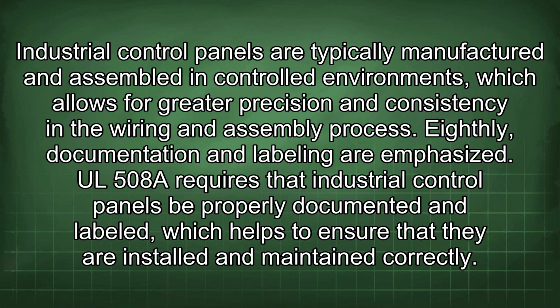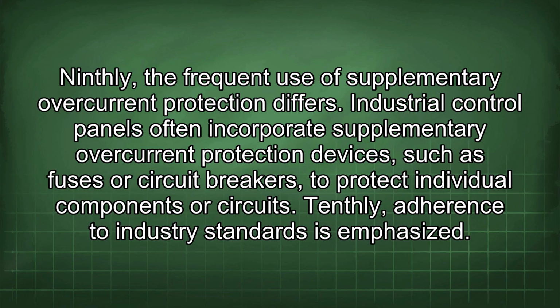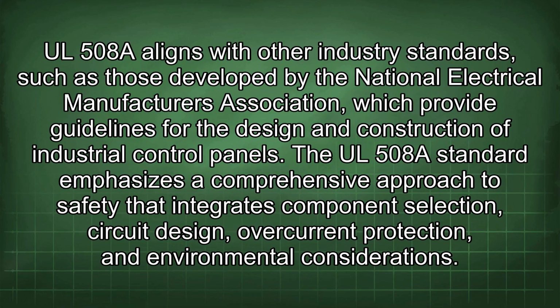UL 508A requires that industrial control panels be properly documented and labeled, which helps to ensure that they are installed and maintained correctly. Ninthly, the frequent use of supplementary overcurrent protection differs. Industrial control panels often incorporate supplementary overcurrent protection devices, such as fuses or circuit breakers, to protect individual components or circuits. Tenthly, adherence to industry standards is emphasized. UL 508A aligns with other industry standards, such as those developed by the National Electrical Manufacturers Association, which provide guidelines for the design and construction of industrial control panels. The UL 508A standard emphasizes a comprehensive approach to safety that integrates component selection, circuit design, overcurrent protection, and environmental considerations.